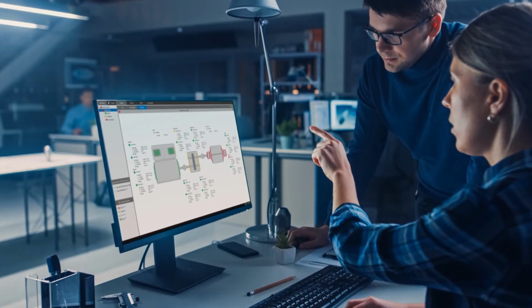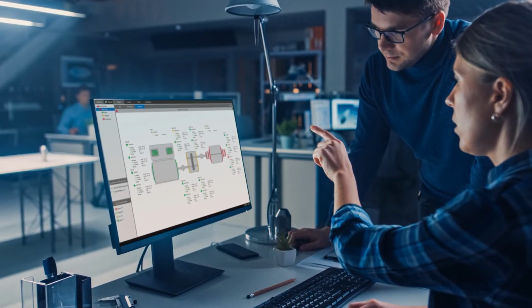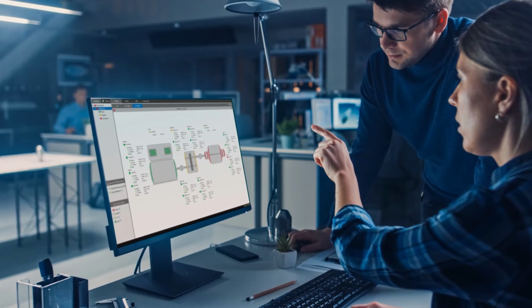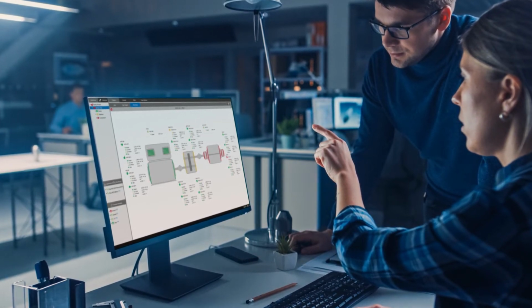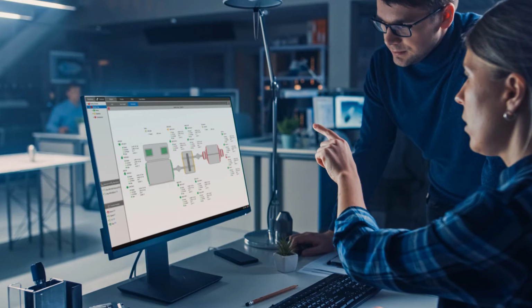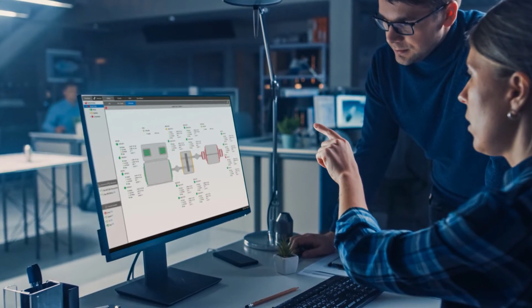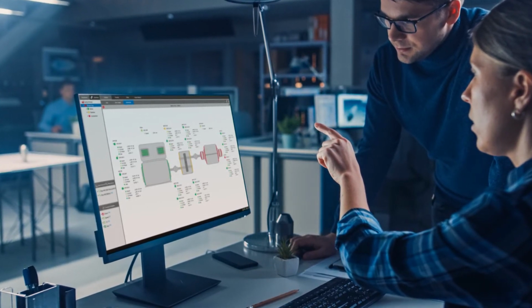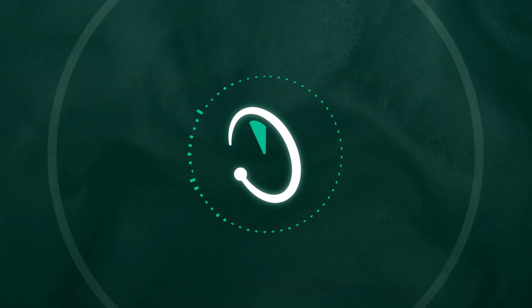Sure, that is another advanced feature that is available. There's no real means for any sensor to know if a machine is on or off without some sort of switch or wire or something else telling it the machine's on or off. So how we get around this or add value here is we sense a minimum vibration level.